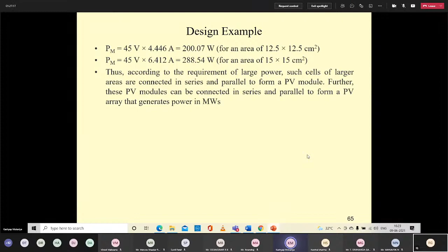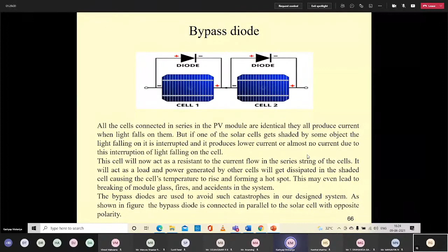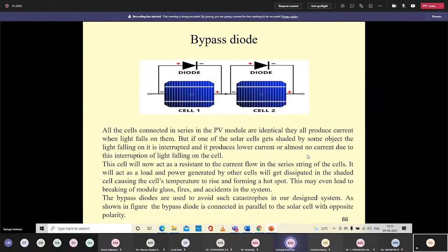All the cells connected in series in the PV module are identical; they all produce current when light falls on them. But if one solar cell gets shaded by some object, the light falling on it is interrupted, producing lower current or almost no current. This cell now acts as a resistance to current flow in the series string, behaving as a load, and power generated by other cells gets dissipated in the shaded cell, causing its temperature to rise and forming a hotspot. This may even lead to breaking of the module glass, fires, and accidents in the system. So bypass diodes are used to avoid such catastrophes in the design system.